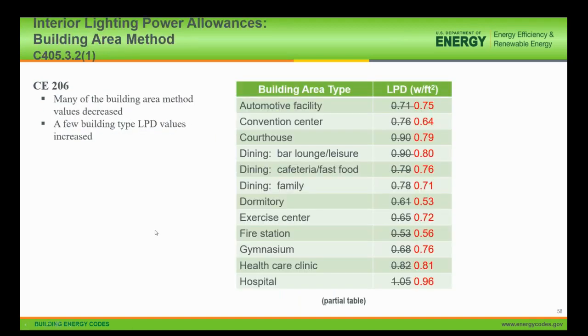Larger changes would be the interior lighting power allowance, the building area method. I say larger because it's a more detailed table, shown here just as a sample of it. It's about twice the size in reality. The black values are the current IECC values. The red will be when the new version is finally published. You'll see that many of the values did decrease. However, some did increase. Automotive facility is a good example of that. It went from 0.71 to 0.75.